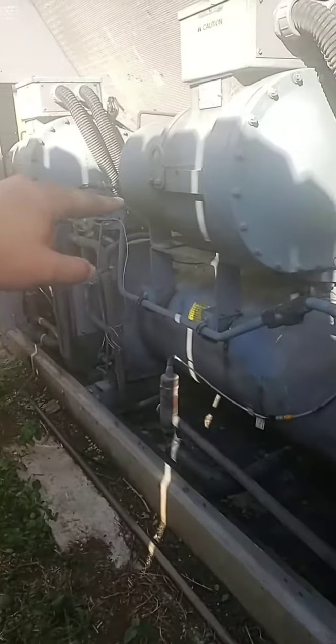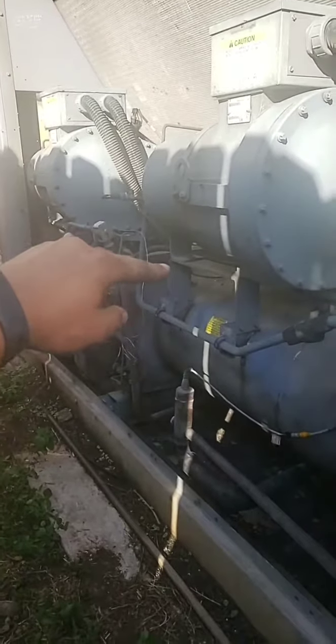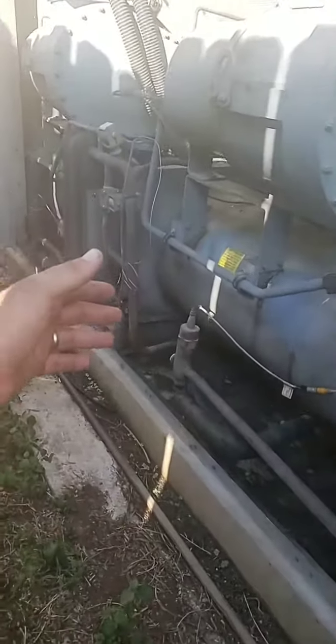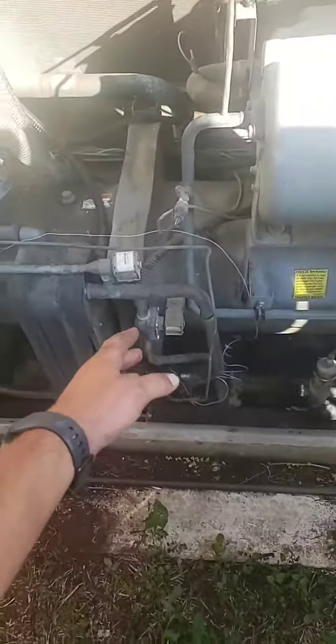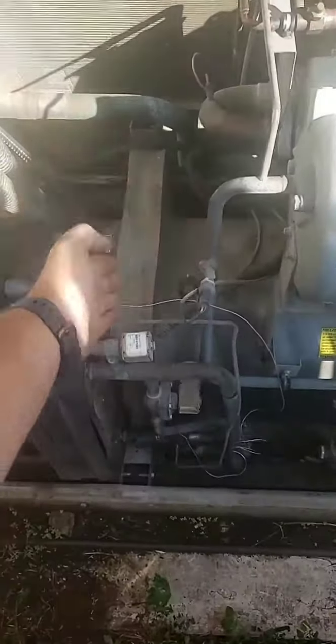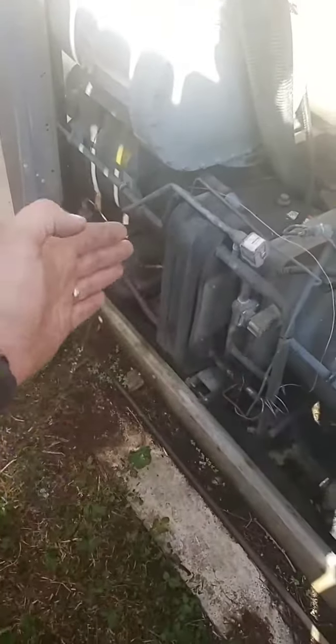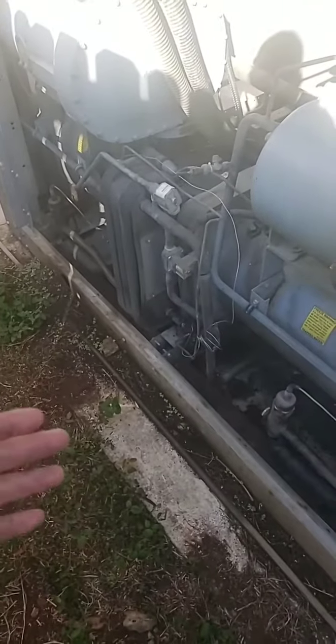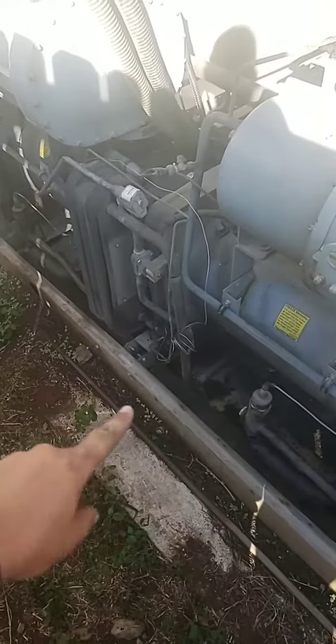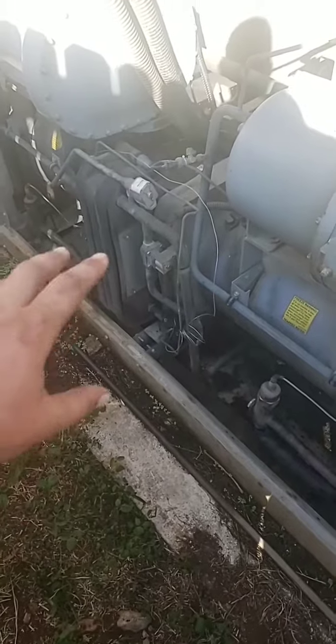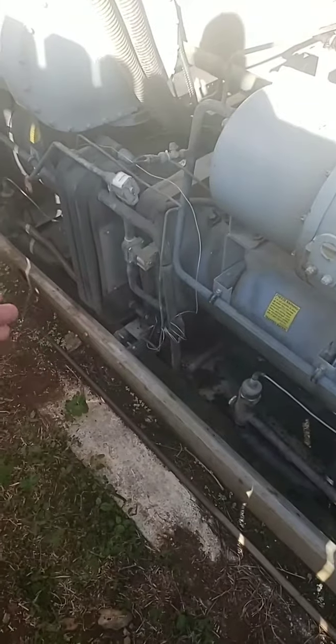First question is how many compressors are there? There are 2 compressors on this chiller. They are 2 separate circuits. One thing unique about this one that you won't always have, but most of your air-cooleds do, is right there on that middle support. That is actually where the refrigerant is split. So you have 2 separate circuits that we're working with. Now, keep in mind, the water tubes themselves do not split. They run straight through and through. The only thing that is split is the refrigerant circuits themselves.